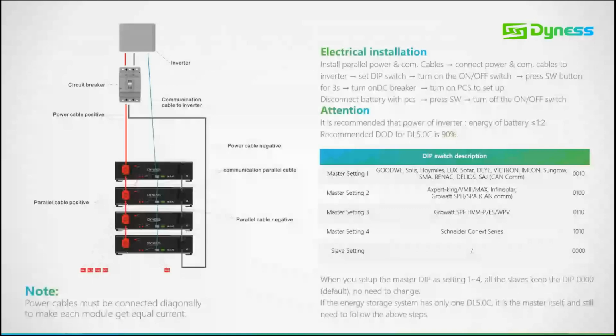Mind that the master battery dip switch needs to be set according to your inverter specifications. The batteries will all be set to 0, 0, 0, 0. Your communication cable will be coming from the inverter to your master battery, from your master battery to your slave battery, repeating this daisy chain until you have reached the desired power required.